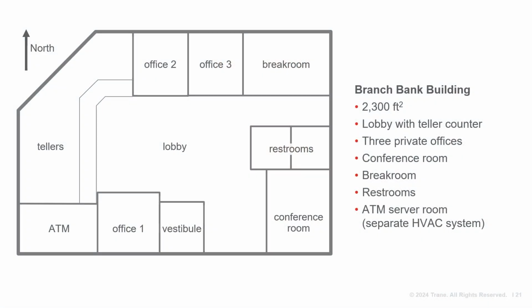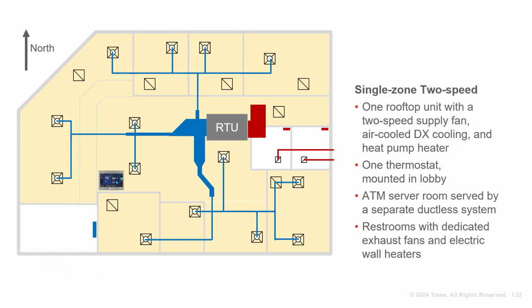Let's use a 2,300 square foot branch bank building as an example. Inside, there's a large lobby with tellers, several private offices, a conference room, break room, restrooms, and an ATM server room. This server room is going to be served by a separate ductless mini split system, and the restrooms will have their own exhaust system. One package DX heat pump rooftop will serve the entire building, as shown here as a single zone in yellow. Supply airflow is ducted to diffusers in the various spaces. Return air grills open to the ceiling plenum allow air to return. For this single zone configuration, a thermostat is installed in one location, the lobby.